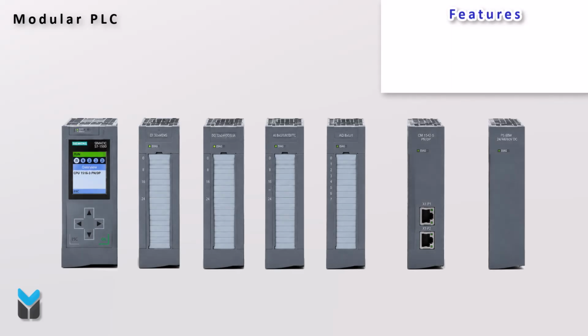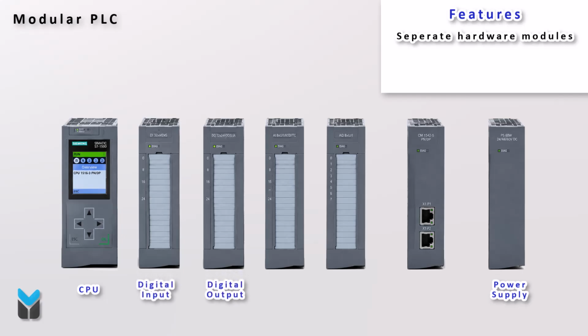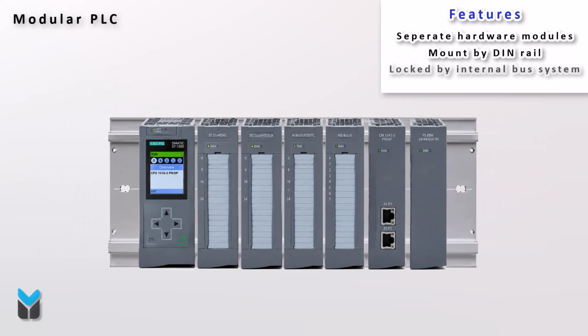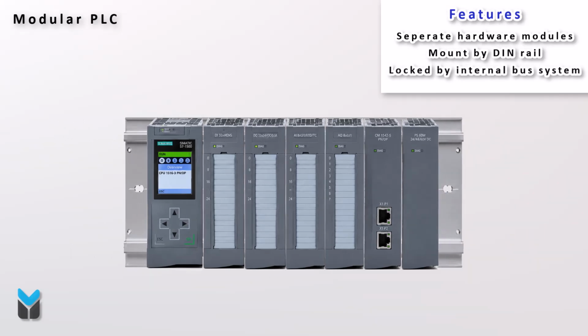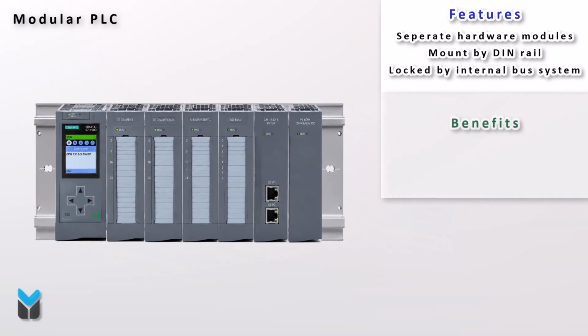Unlike the all-in-one approach, a modular PLC breaks the system down, separating different functionalities into individual hardware modules. In this setup, you have a distinct module dedicated entirely to the CPU, another for the power supply, and completely separate modules for digital I/O, analog signals, advanced communication, and precise motion control. These modules are mounted side by side on a DIN rail and locked together through an integrated internal bus system. This modularity provides immense engineering flexibility and scalability.